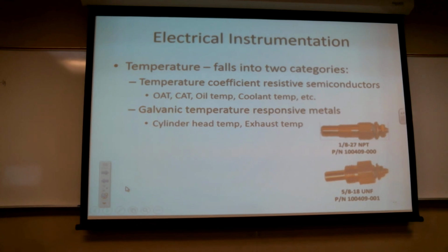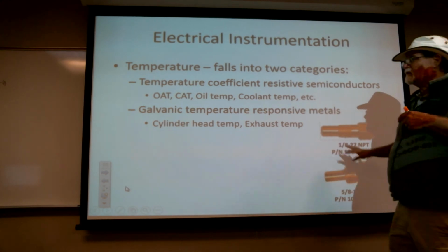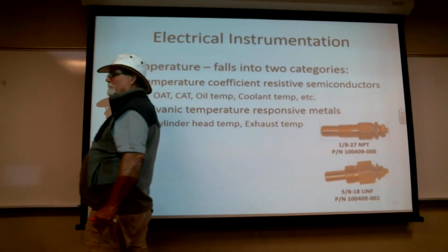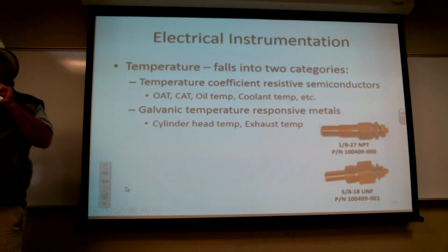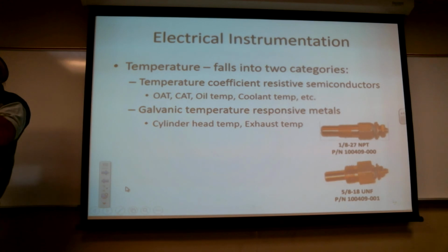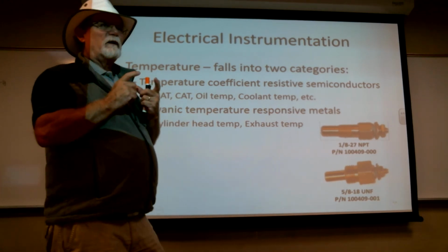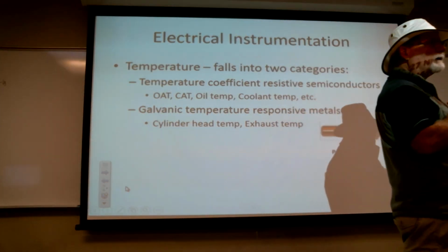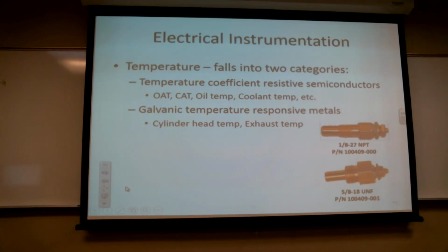The other thing that's sort of awkward about this is I've got these two wires, one made out of Constantan, the other made out of iron or whatever. I've got to run them from the gauge all the way out to the airplane, to the engine, to whatever it's stuck into. Well, it turns out that with these particular devices, I can cut the wires and patch a piece of copper wire in there. That's also going to form two additional hot and cold junctions, but they're going to affect equally, so they're not going to distort things too much.